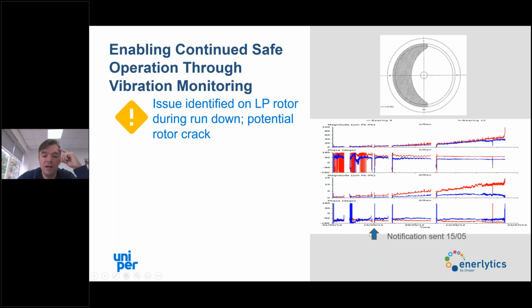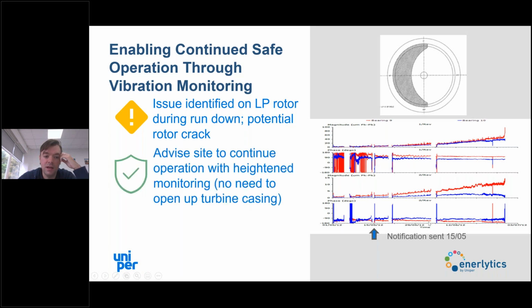Around May time, we identified a potential rotor crack. There's no way of knowing if this is the case because you've got to open up the turbine and you've got to cut the rotor in 2 to see, and at that point it's pretty much useless. So they had a planned outage at the beginning of July, and based on our vibration data and the temperature data, we enabled them to continue to run safely for another month.